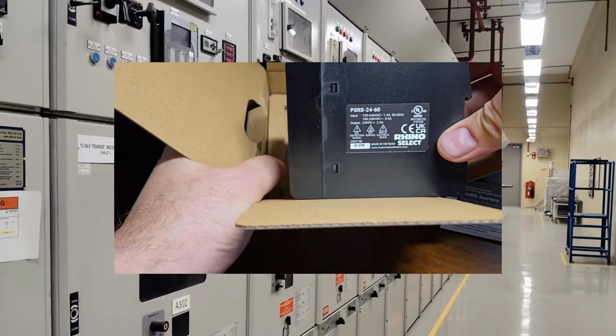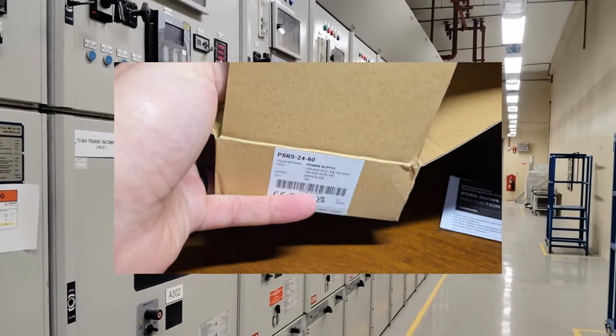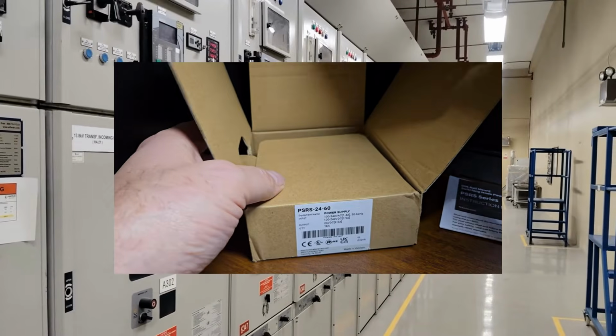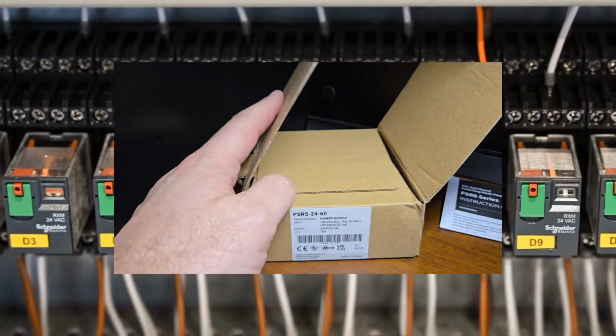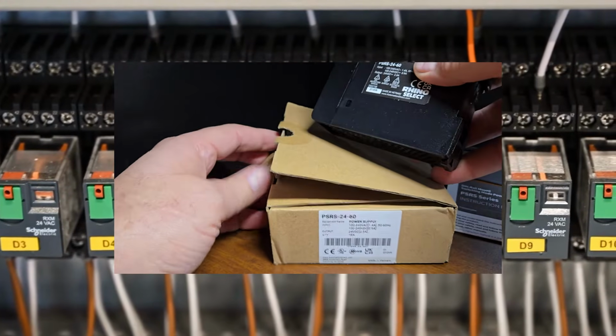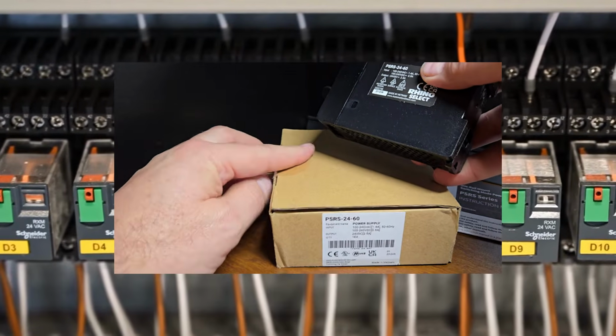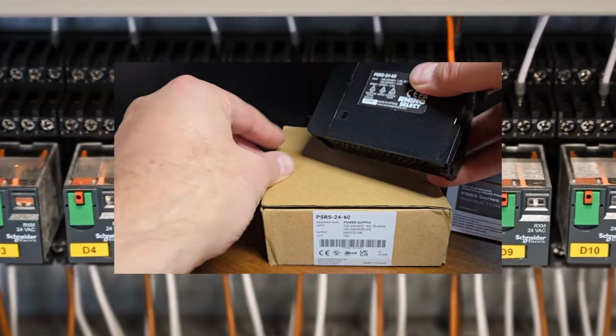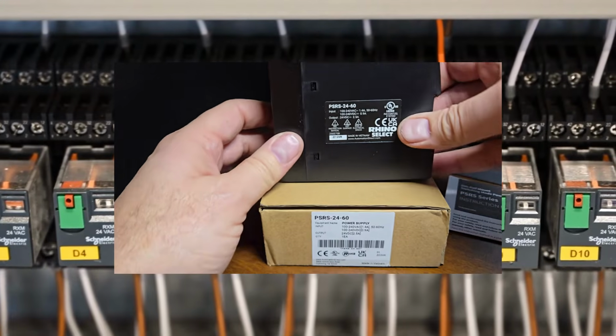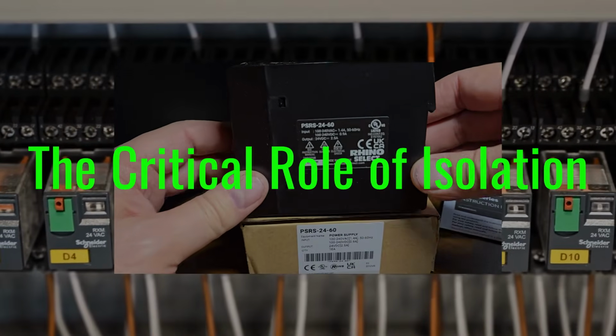You cannot simply plug a sensitive DC sensor into a 480V AC line. You need a bridge that does more than just convert AC to DC. You need a device built to withstand the heat, vibration, and electrical noise typical of a factory floor, all while providing unwavering voltage regulation. The critical role of isolation beyond just converting voltage.